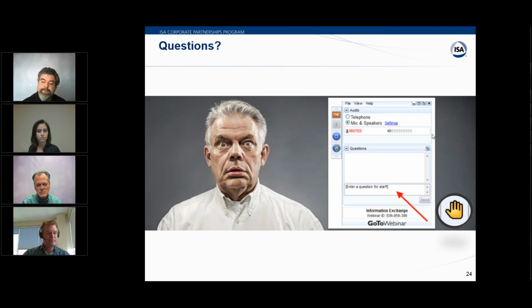Thank you, Ian. Roy, during your demo, one attendee wanted to verify that the pH transmitter is sending a milliamp signal to the calibrator. So that is true, and I didn't actually point that out. There are a couple of leads coming out of the transmitter going into my calibrator, and that's how I'm measuring the current. But that is true.